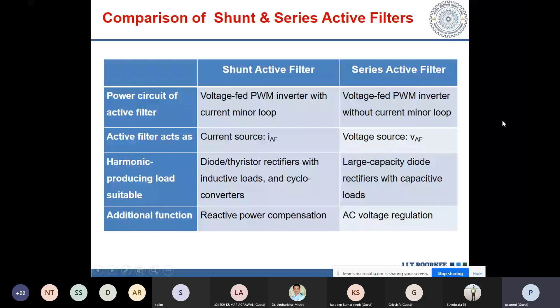You can also use hybrid, because if you are using active filter alone, the problem is active filter is made of switches, and if high current is switched on or switched off, then the switching losses will be more. So what is done normally, that this active filter is put in parallel with the passive filter.